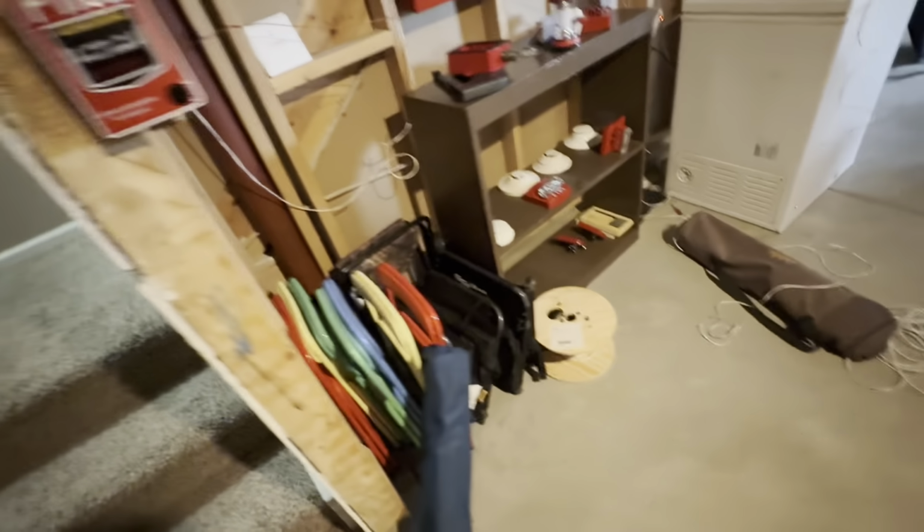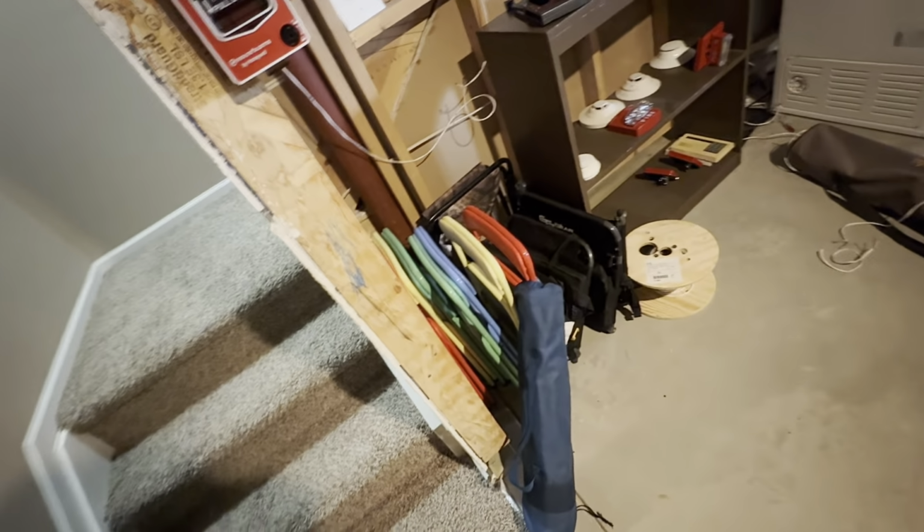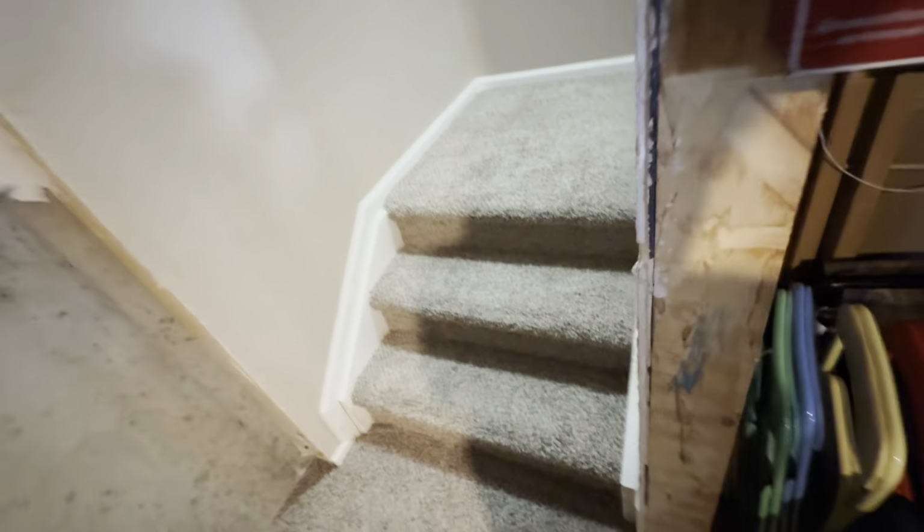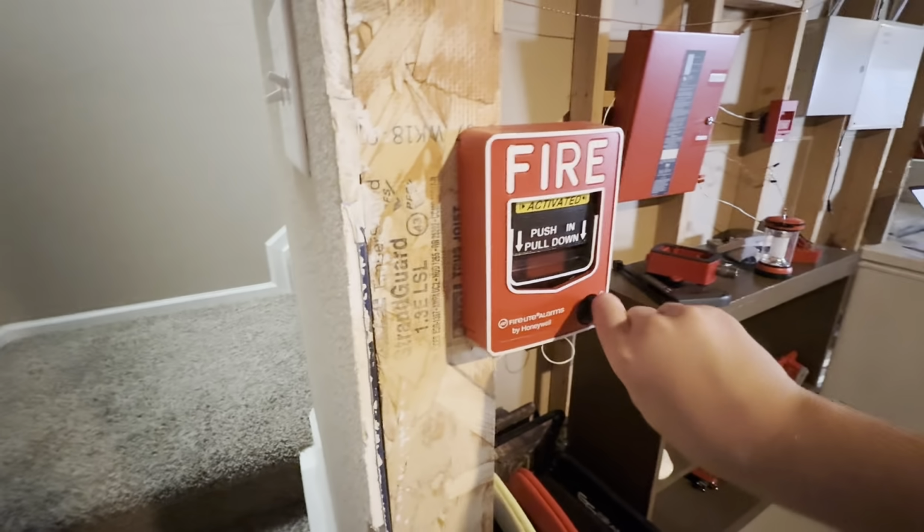There, so you could hear that L series give that little chirp when I hit silence. That's just because it's both on NAC 4, so one of them gets power cut like a millisecond later.